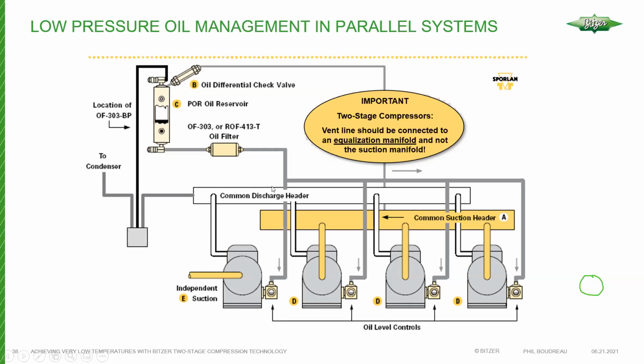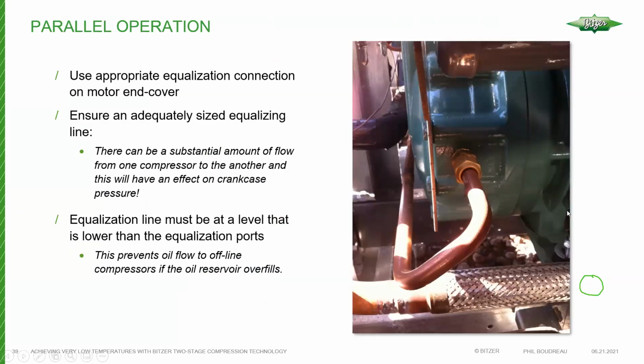Unlike a single stage system, when you're using a low pressure oil management system on a two-stage parallel system, you want to make sure that you have your vent valve. In this case, it's an oil differential check valve, which operates on a differential pressure, usually 20 psi or so. Or if it's a regulator that operates on a pressure difference, you want to make sure that you use your interstage as the reference pressure and not your suction header, because remember, your crankcase is at interstage pressure. If you're venting the oil reservoir down to suction pressure plus 20 psi, you'll never get any oil flow into the oil level regulators. In fact, when the regulator is open, if anything, the oil is going to leave the compressor and go back towards the reservoir. And we certainly don't want to do that.